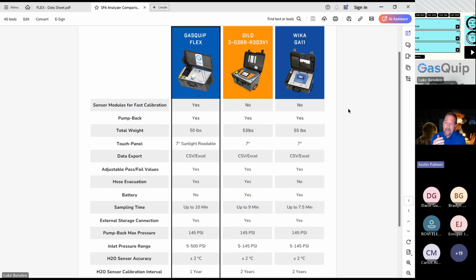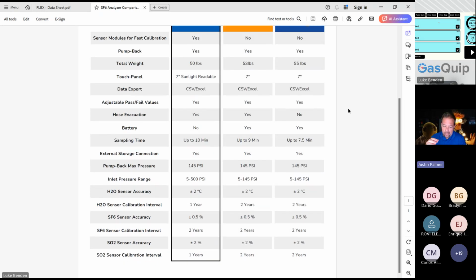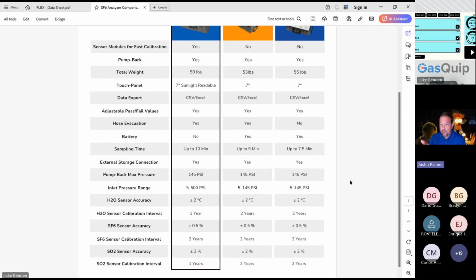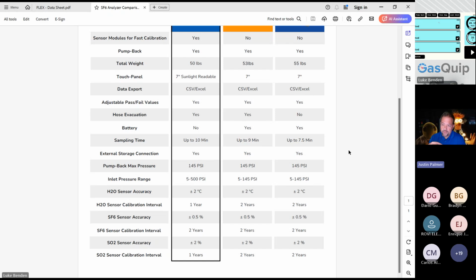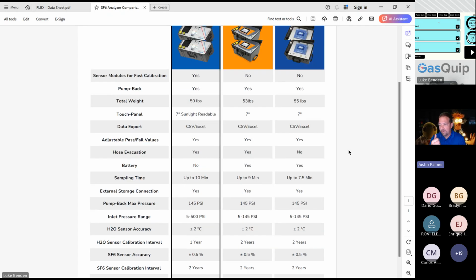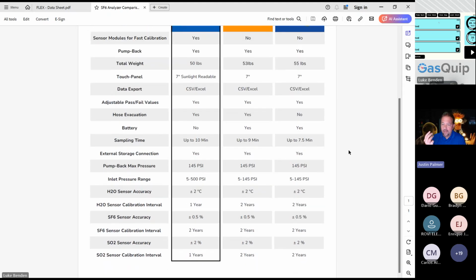Anything wetter than that, meaning you'll see a lower negative value, is plus or minus 2 C. Once you get below that minus 40 threshold, it goes up to plus or minus 3, because if you start looking at a dew point chart, the values are much closer to each other as you get into the drier gases. So they've got a little bit more of a spread down there. And on the wetter ones, it's a little bit tighter because there's a lot of wiggle between those. So that would be the same for Dilo, Wika, SMC, whoever else I left out.